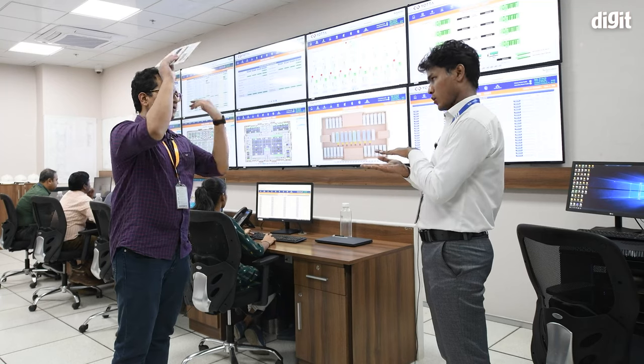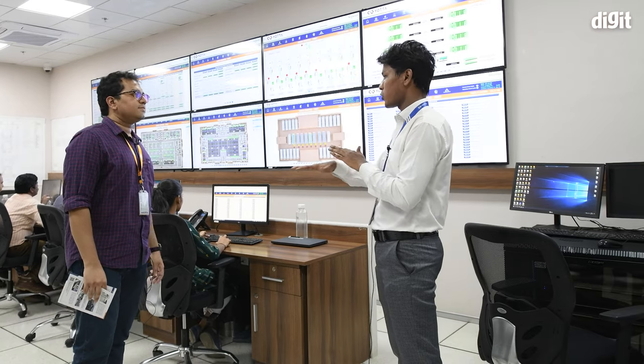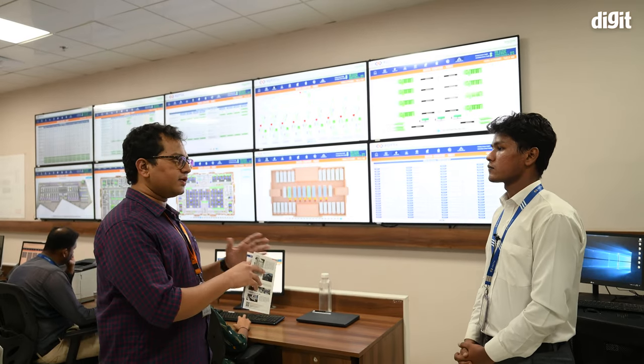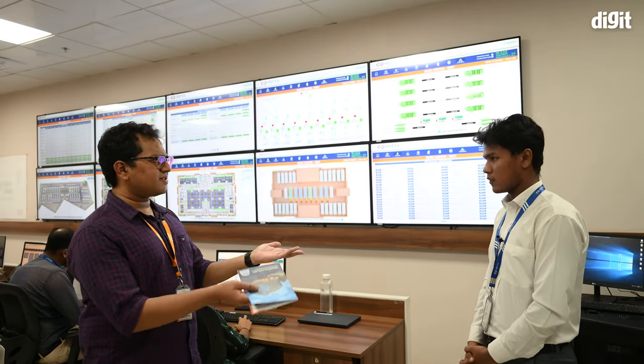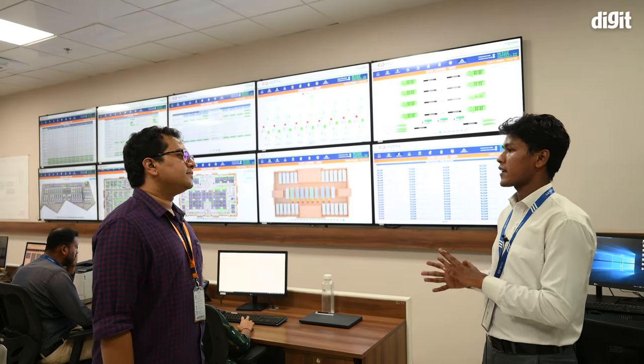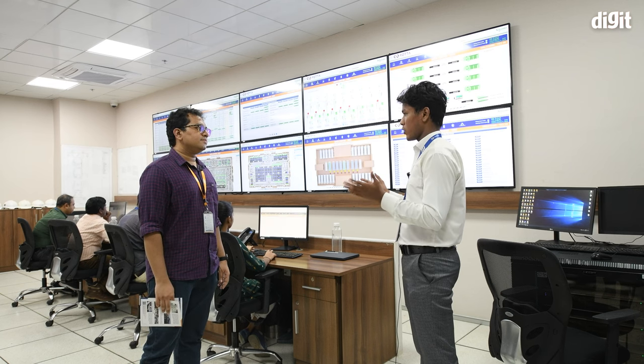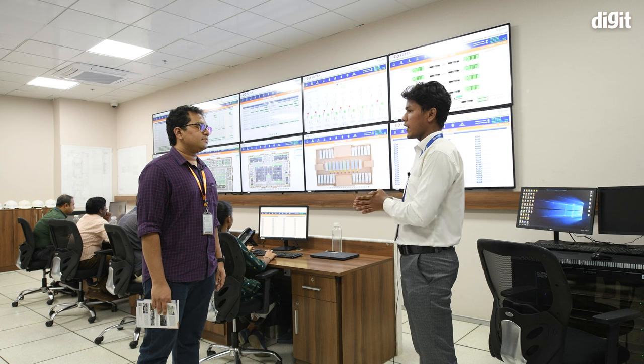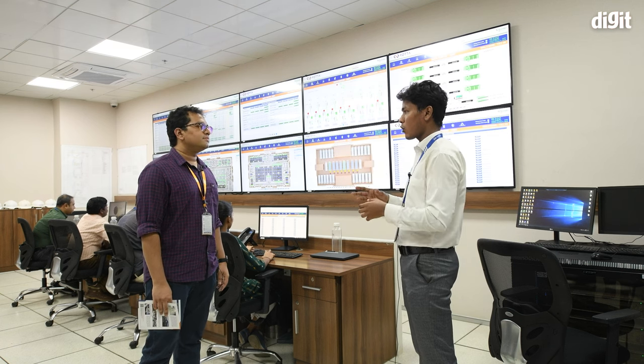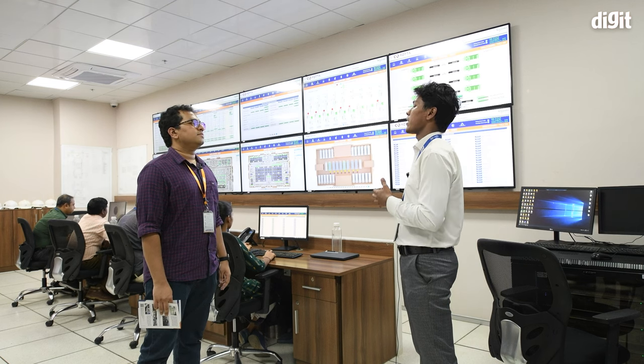It's a massive sandwich of sorts — each pair of utility and server floors acts as an individual data center, so anything happening on one floor will not impact the other. Every floor is divided into an A side and B side. Either side alone is capable of running that floor; the other side provides active redundancy. In active redundancy, both sources are live and sharing the load. When one fails, the other takes the entire load.